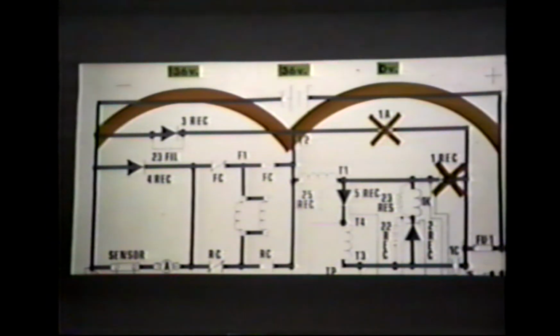If the voltage is lopsided and there are 0 volts from T2 to positive, check for a welded 1A contactor or a shorted 1 rec. If no faults can be found, replace control card. Also, if the voltage split is even, but there is no voltage from R3, replace the card. The next symptom is similar to the preceding one, except that this time the directional contactors do close, but there is no power and no SCR hum.